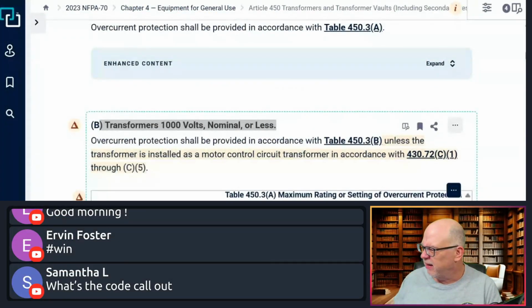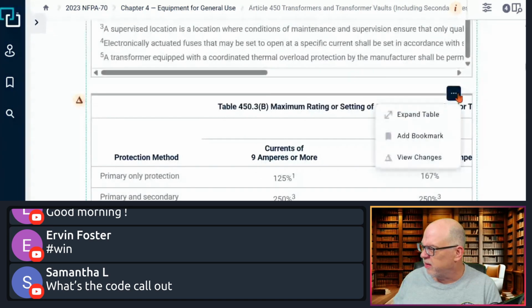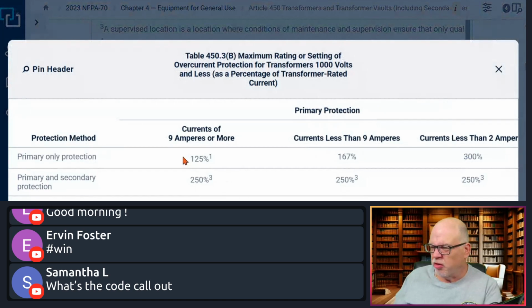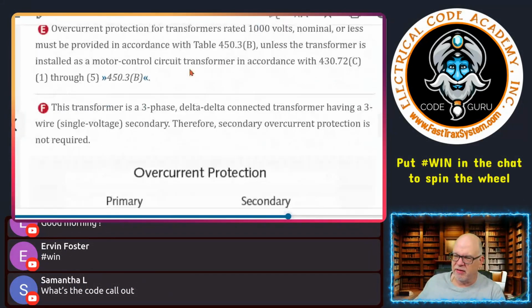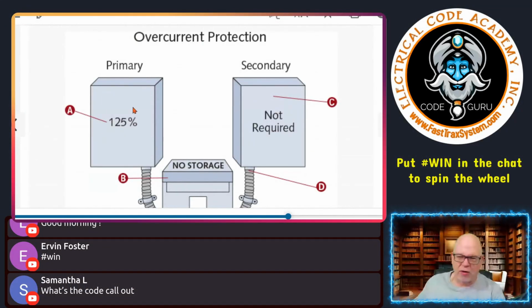All right, so where are we at? Here we're at the ratings. So let's pull this table up, for what piece of the table you can actually see. So this is what it's talking about. If it was primary only protection, meaning all we had was primary only protection, then this is what we're talking about down here. If this is primary only protection, then I can go up to 125%.